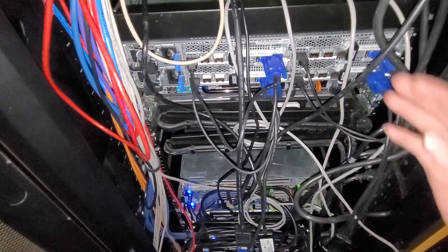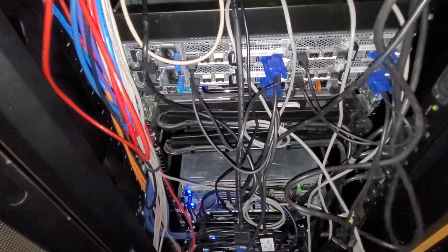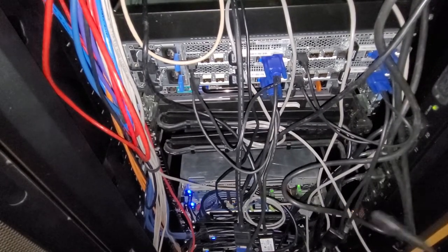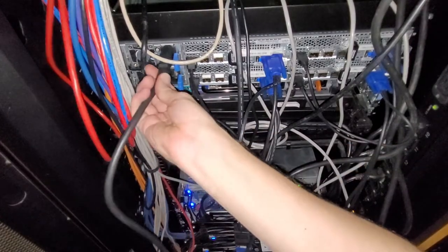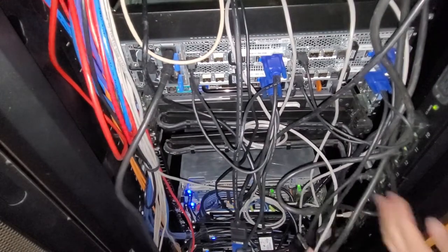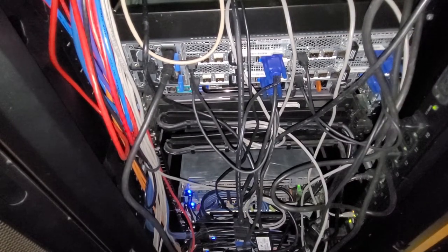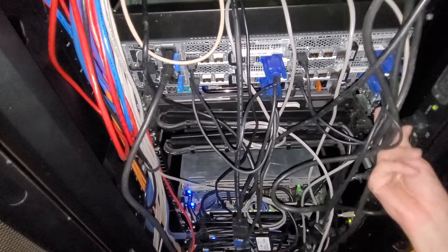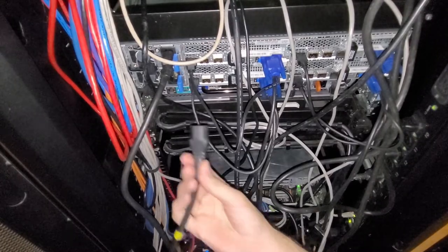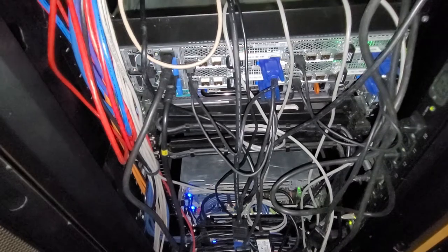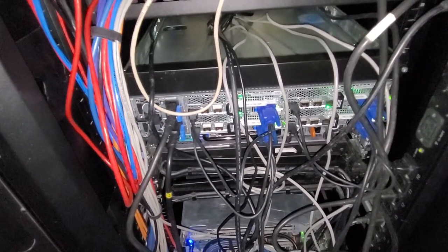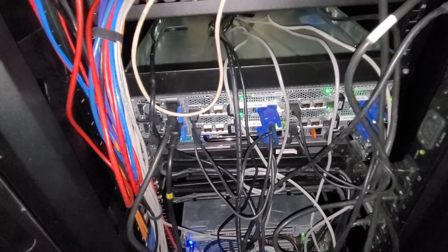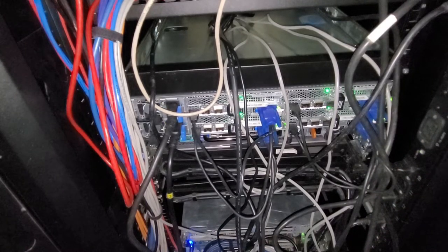Now, the tricky part is finding the cords for that particular server. Alright. That's one of them. And there's the other one. The problem with this C6320 is it's 220V only. So I have to be mindful. There are a few things in this rack that will only run 120V. So I have to be really careful with these 240V PDUs I'm running.